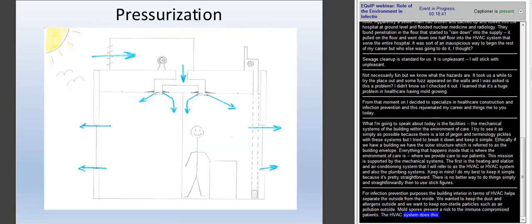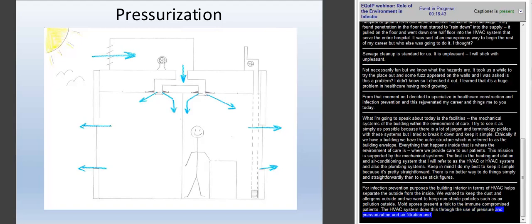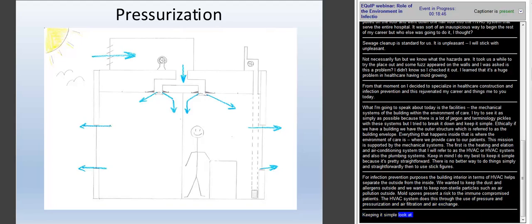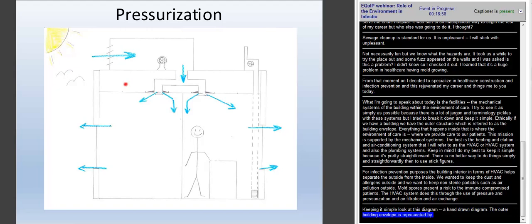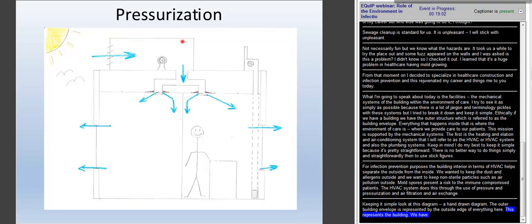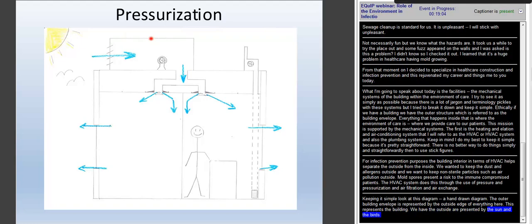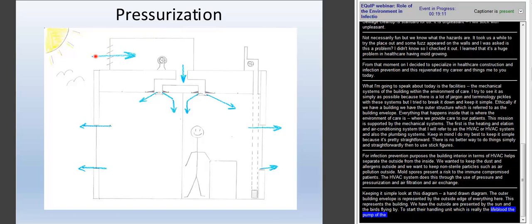So keeping it simple, if you'll look at this beautifully hand-drawn diagram, we have the outer building envelope as represented by the outside edge of everything here representing the building. And we have the outside represented by the sun and the birds flying by. And so to start, the air handling unit, which is really the lifeblood, the pump of the HVAC system, is typically found on roofs, not always, but generally on roofs, and fresh outdoor air is drawn in through a set of louvers by a fan that's inside the air handling unit.